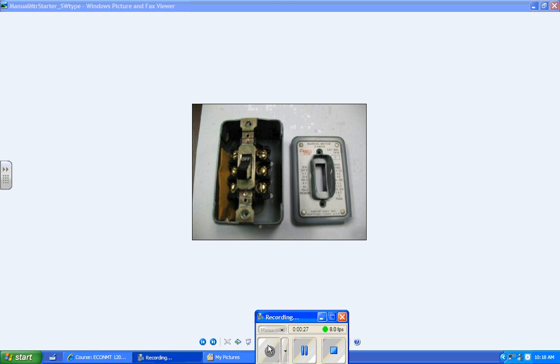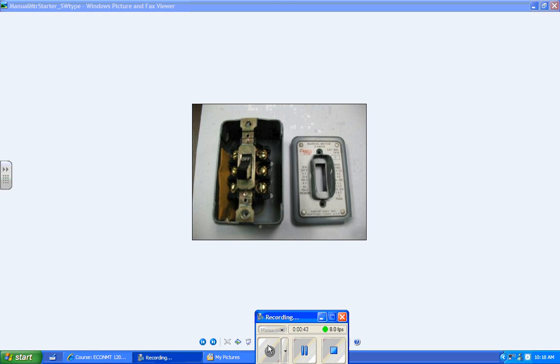Some of them are so small that they will fit in a light switch box, and this picture is one that fits in a light switch box. What is the difference between this manual motor starter and a light switch, a really heavy-duty light switch? It's got a built-in motor overload. It's got overload temperature protection built in.